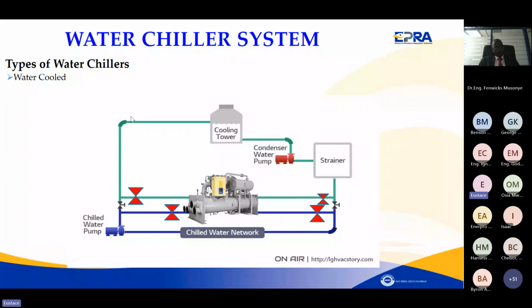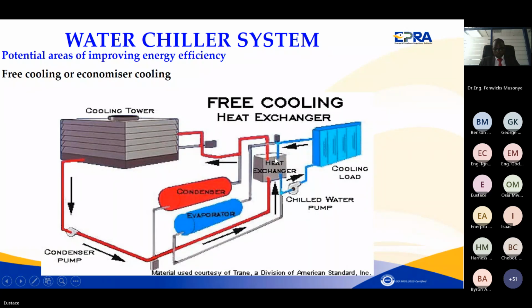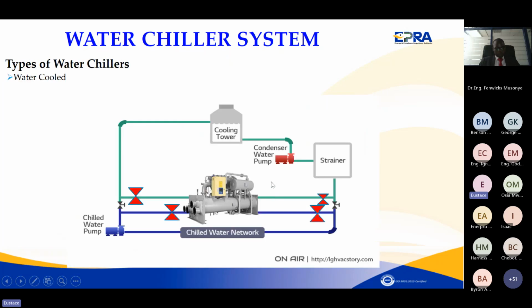And this is a good diagram showing how you can bypass. You can get the water from the cooling towers to the pump. Instead of taking it to the condenser, you stop the chiller, you close this valve and this one, and allow water to go to the chilled water network directly. If you are sure it's not going to interfere with the quality of water, and the quality of the chilled water cycle and the quality of the condenser water is the same, you can do it like this. But if it's not the same, you can introduce a heat exchanger in between to ensure that there is no mixing between the water from the evaporators and the water from the condenser. So bypassing the chiller system, the refrigeration cycle, is good, and that is what we normally refer to as free cooling.